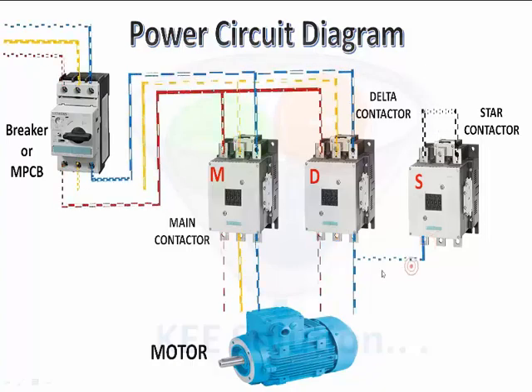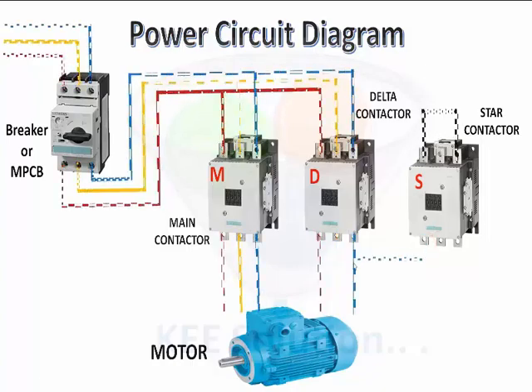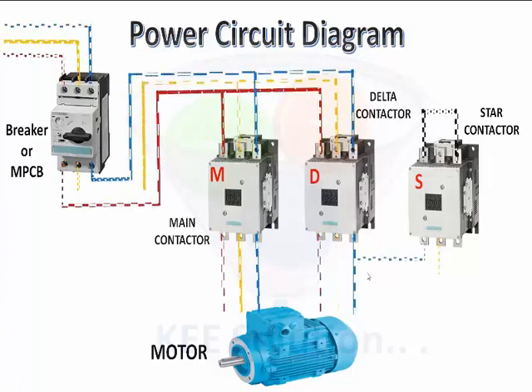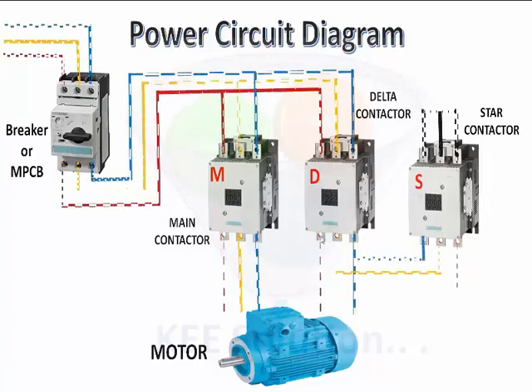Here it is important: in the star contactor, the first phase should be blue in place of red, and it should be connected to the blue terminal. Yellow should be connected to yellow, and red should be connected to red.